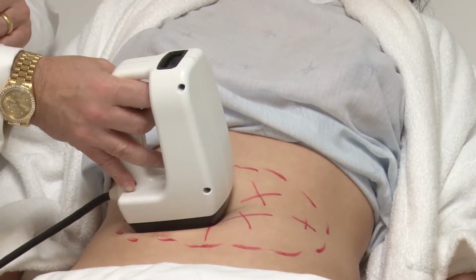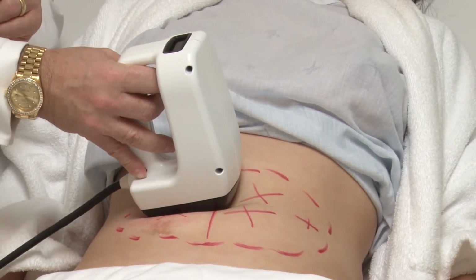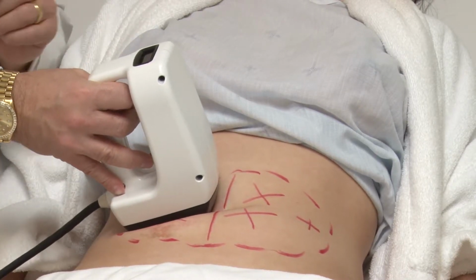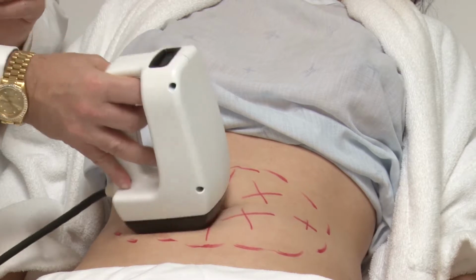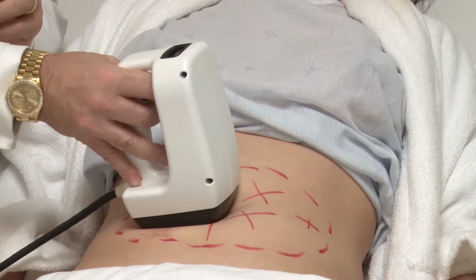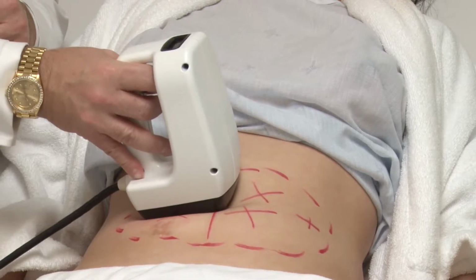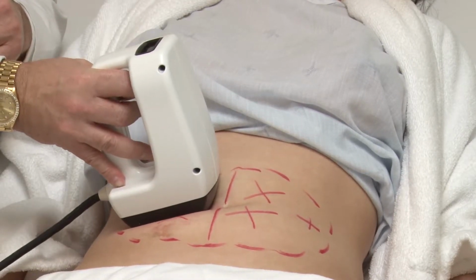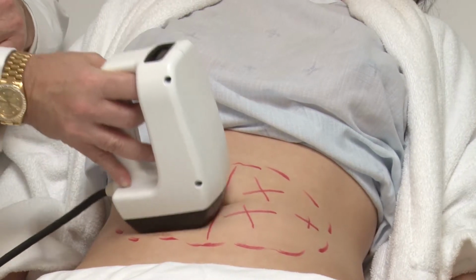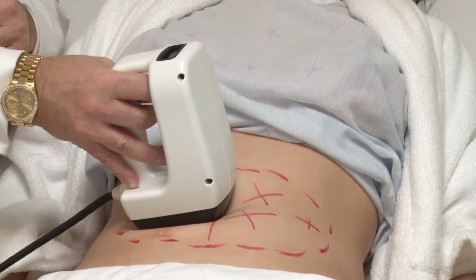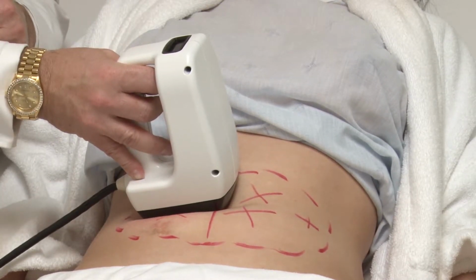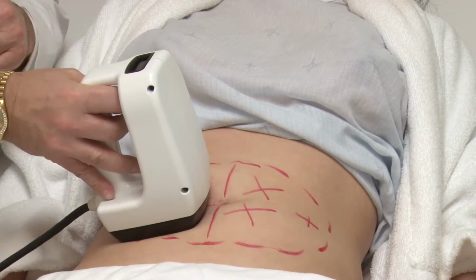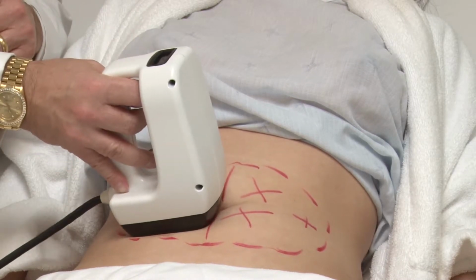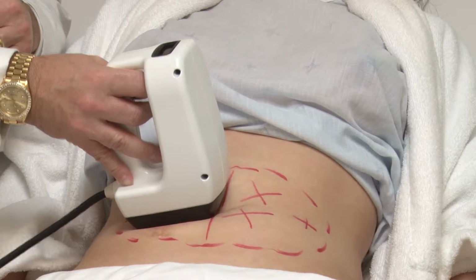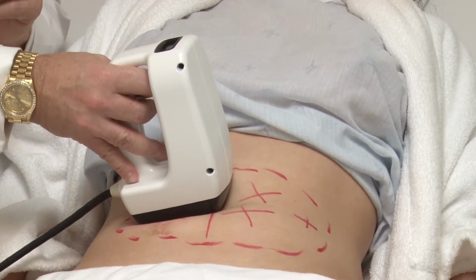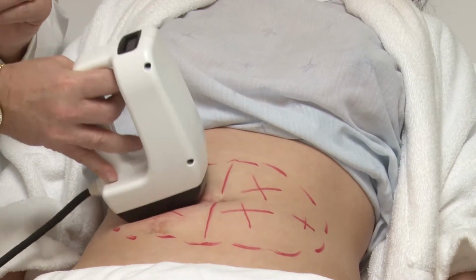I'm going to warn the patient that we're going to get a high voltage pulse at 42 degrees, and I tell them, that's killing your fat, very loudly, because when they know it's killing their fat, they're more likely to tolerate a different sensation than something that seems random. So we're at 40 degrees now. You're going to start to hear some double beeps. And in a second, you're going to hear some double beeping. There's double beeping. And so about a minute you can get your endpoint. We're almost 42. So you're going to feel an electrical shock in a second right there. That electrical shock is a high voltage pulse.